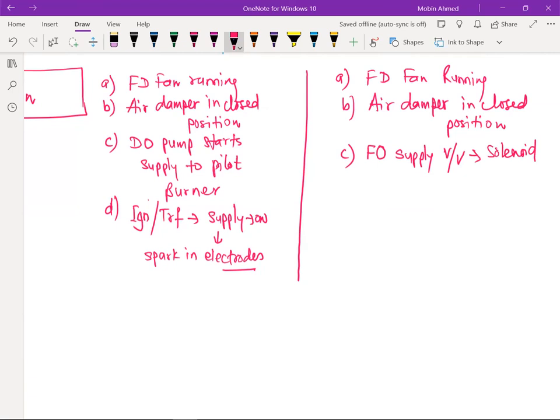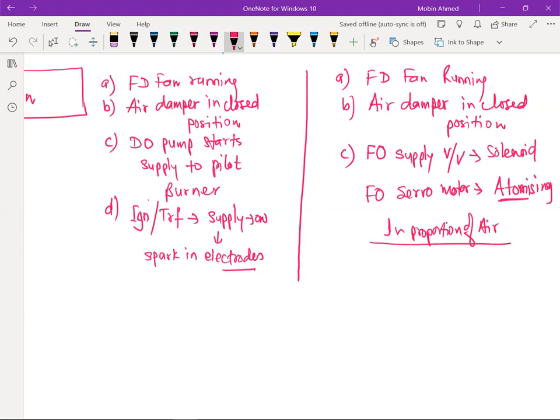So this is going to be atomizing type. This is going to be on. Okay, it is going to be on. And once it is on, thereafter there is a servo motor also there, the FO servo motor. So this servo motor will be operated accordingly, because your air is not there. From the nozzle, it will manage the fuel in such a way that it will be in proportion. So this is atomizing, but it will be in proportion of air. Because the air damper is closed, in proportion of air this servo motor is going to work. So accordingly, it will come to the atomizing.